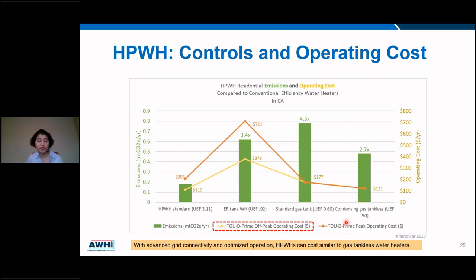From an operating cost perspective, if you're using all the heat pump water heater capabilities—grid connectivity and the controls that come with the latest models—the takeaway is that with advanced grid connectivity and optimized controls, heat pump water heaters can cost almost the same as tankless water heaters. That's the blue line and the yellow line comparing operating cost.